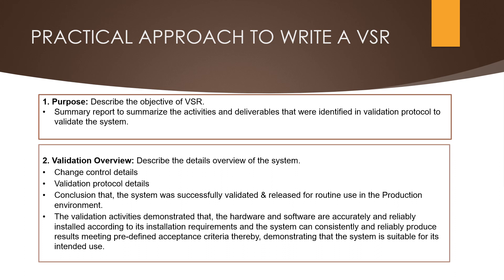The second component is the validation overview section. Here we need to describe the details overview of the system such as change control details — that is change control number, change control initiation and approval date. Next, we need to describe the validation protocol details — that is validation protocol number and its execution status. We also need to define the conclusion statement, that the system was successfully validated and released for routine use in the production environment.